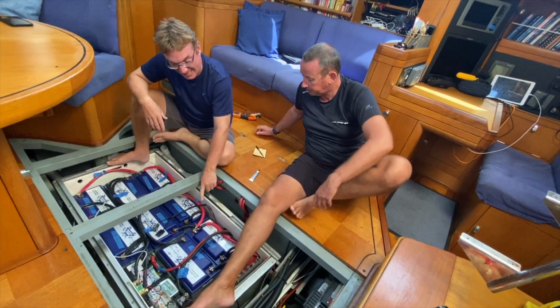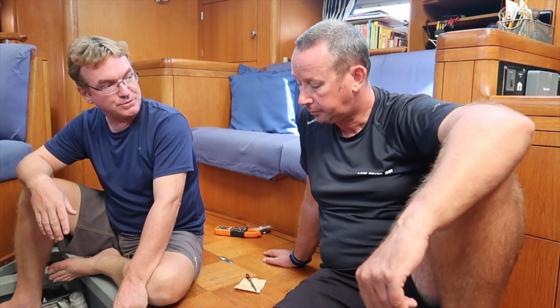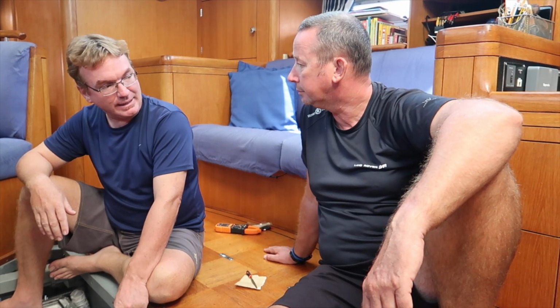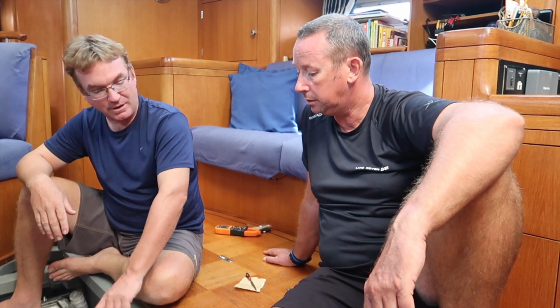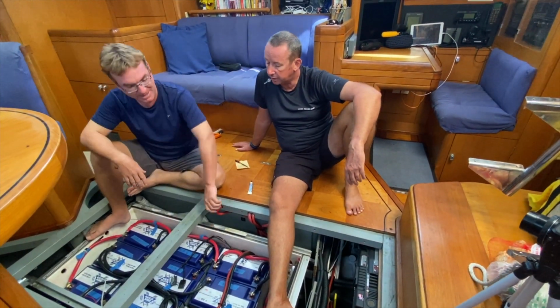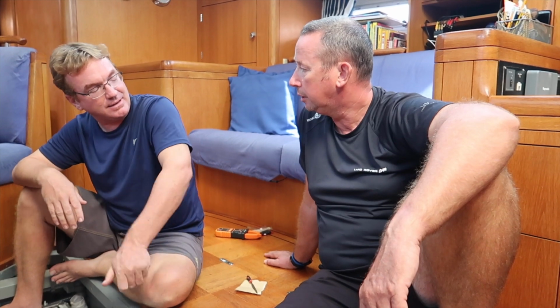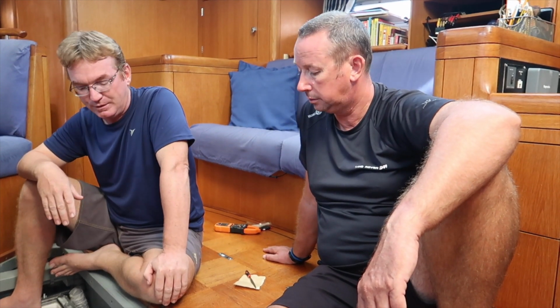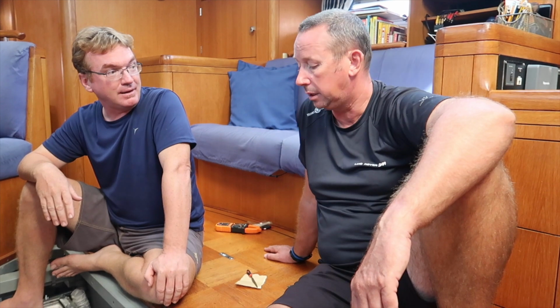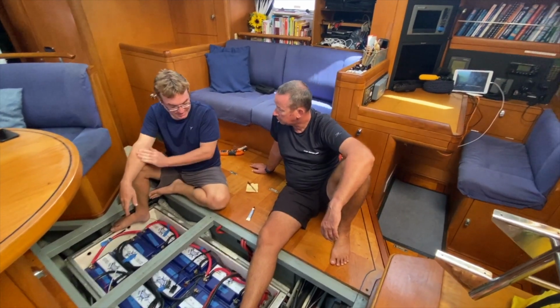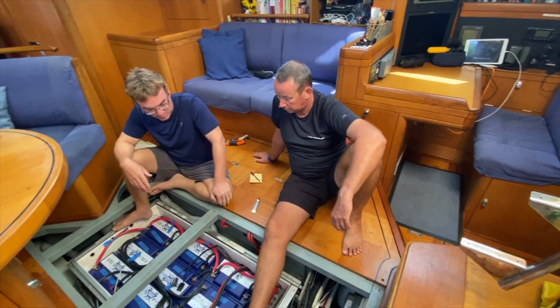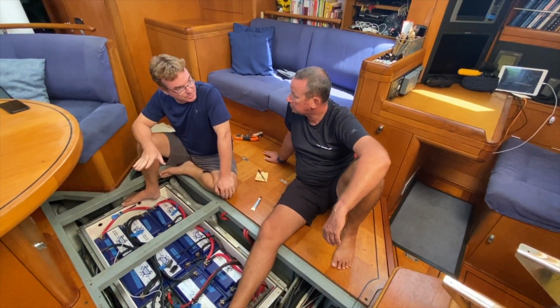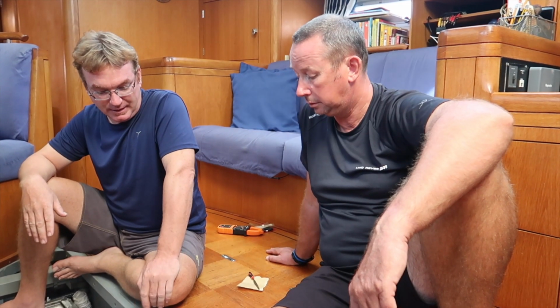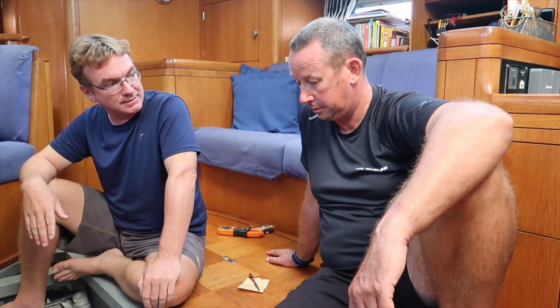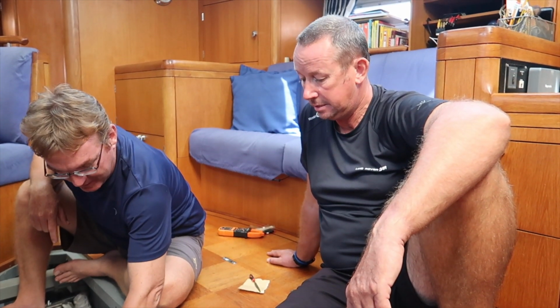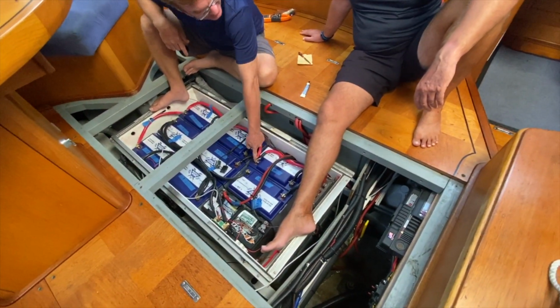That's great. Any wire over 6 AWG, you're not allowed to use wing nuts on the battery. Oftentimes I'll see them used because they seem handy, you can tighten and loosen them by hand, but anything over 6 gauge, don't use a wing nut. I recommend you don't ever use them. ABYC says anything over 6 gauge, you're no longer within standards. You want to use a good, properly sized bolt, a lock washer, and a nut, and never put a washer between the face of your battery lug and its mating surface.